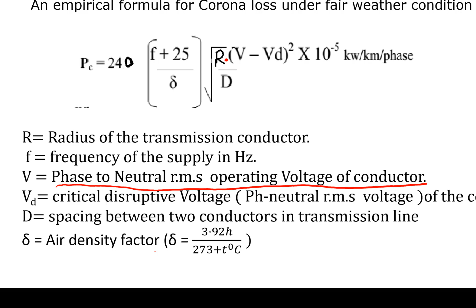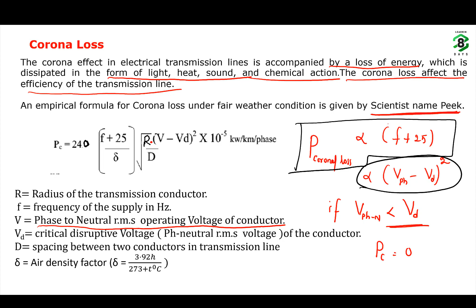What you have to remember is that corona loss is directly proportional to frequency plus 25, which is very important, and to the voltage difference between the phase to neutral voltage of the conductor and the critical disruptive voltage. If the phase to neutral voltage is less than the critical disruptive voltage, corona will not occur and corona loss is 0. Corona loss increases with the frequency and the difference between these two voltages. Even in HVDC conductors there is corona loss, but it is very small compared to HVAC because the frequency in HVDC lines is 0.